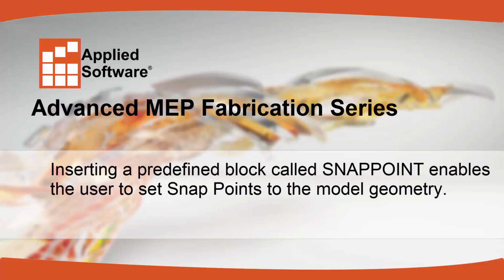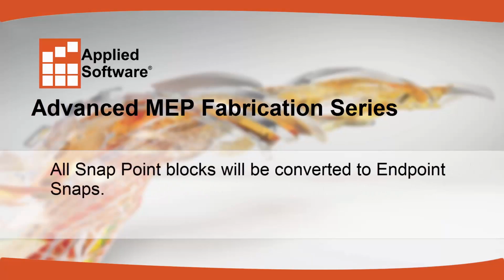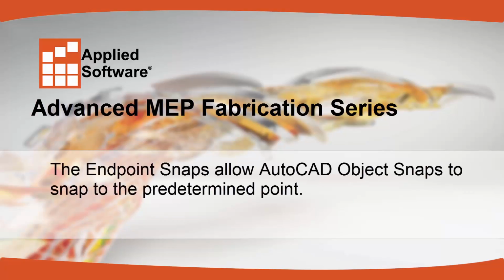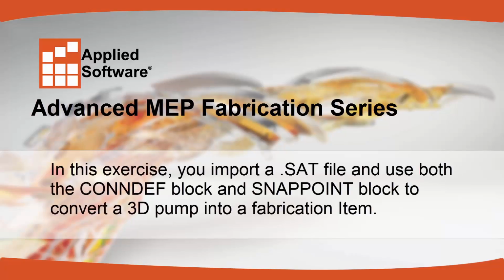Inserting a predefined block called snap point enables the user to set snap points to the model geometry. All snap point blocks will be converted to endpoint snaps. The endpoint snaps allow AutoCAD object snaps to snap to the predetermined point. In this exercise, you import a .sat file and use both the CONNDEF block and SnapPoint block to convert a 3D pump into a fabrication item.